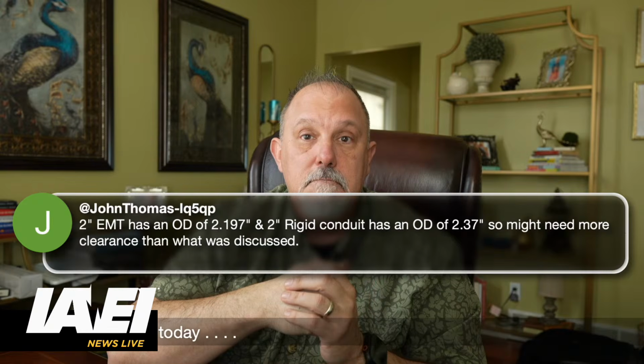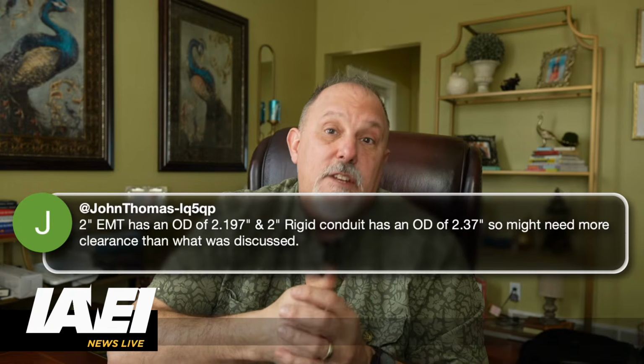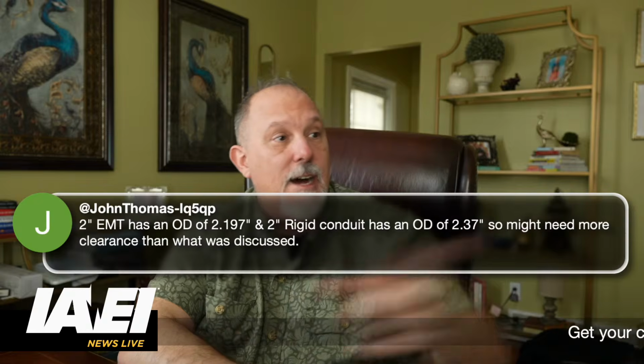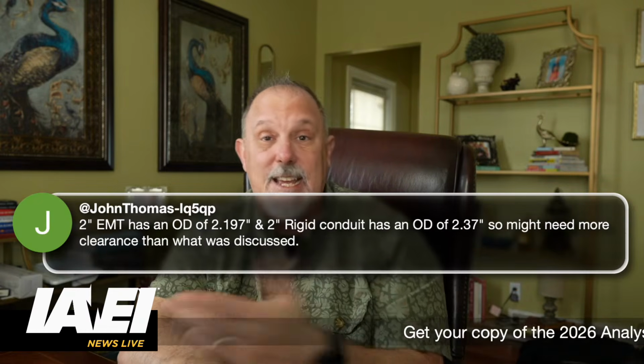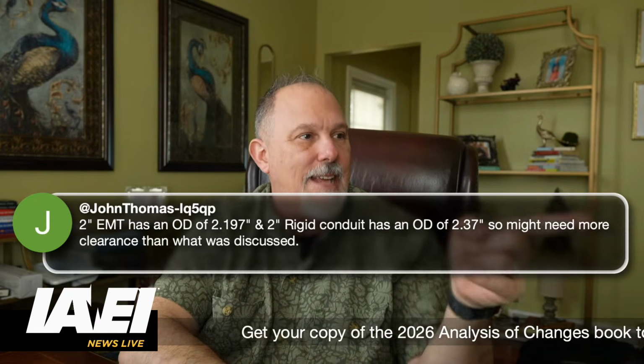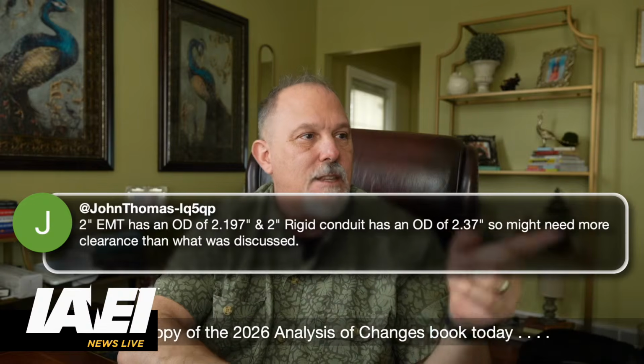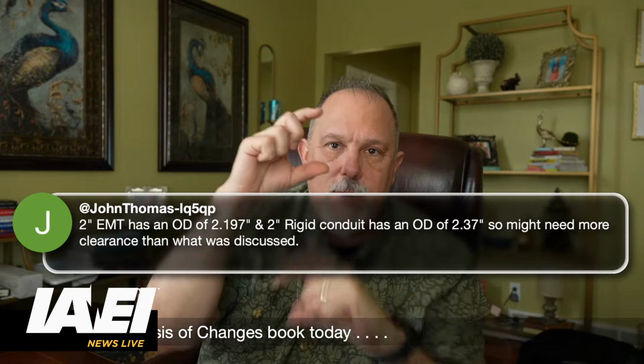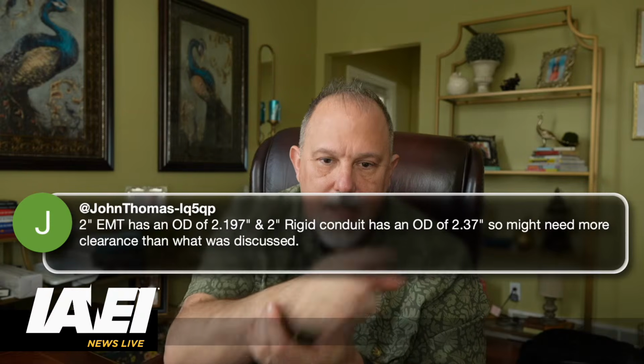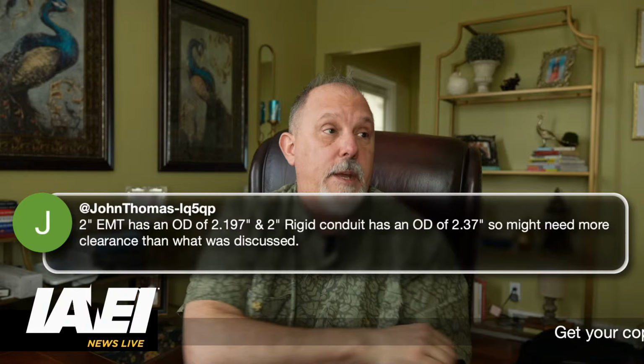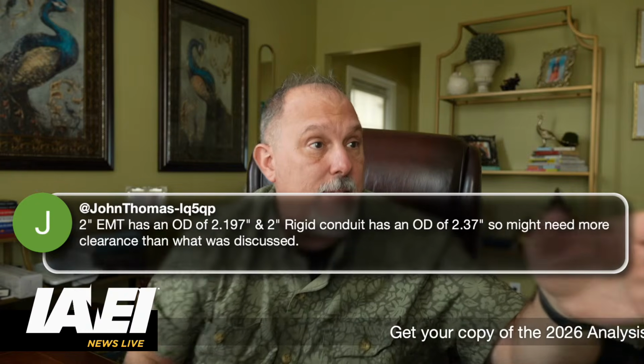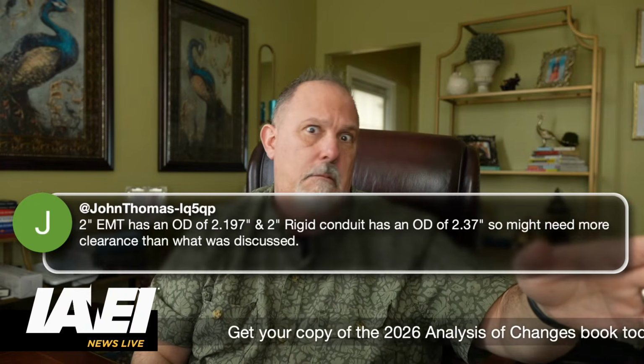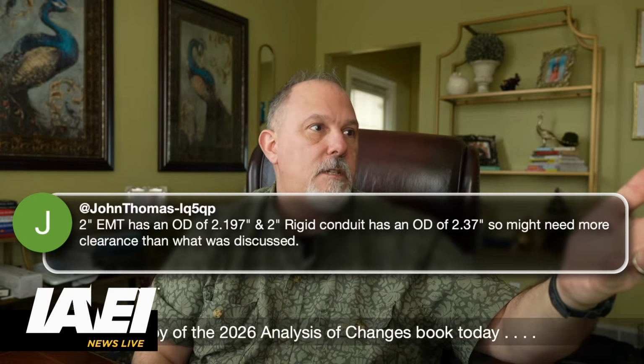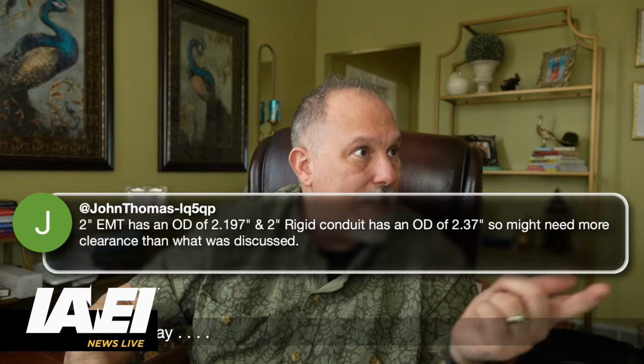Can't see it. I've only got 2.5 inches. I don't have a minimum of, I've exceeded the minimum of 2 inches thick, but it doesn't say that the 2 inches has to be on top and bottom of the raceway. And in the case, and now it could be that the code panel is saying, look, it doesn't matter because it's in a concealed location. But the whole purpose is protection from nails coming in top and bottom because it's in E.